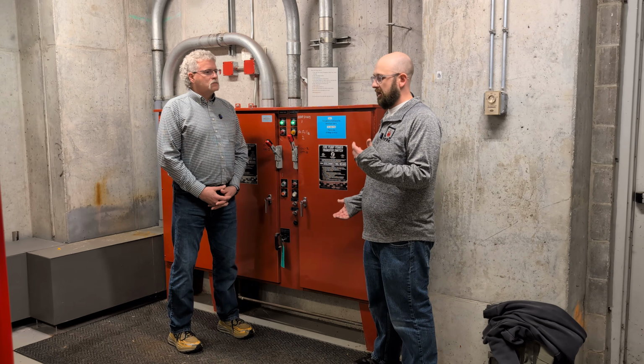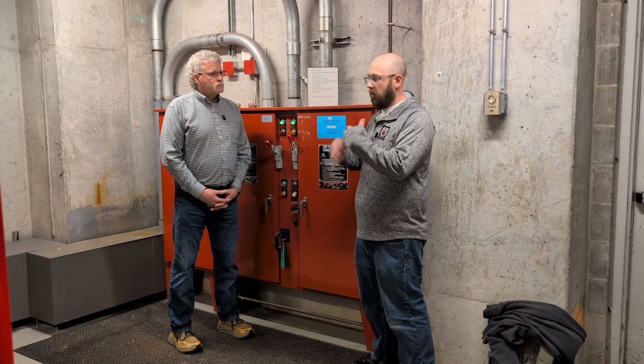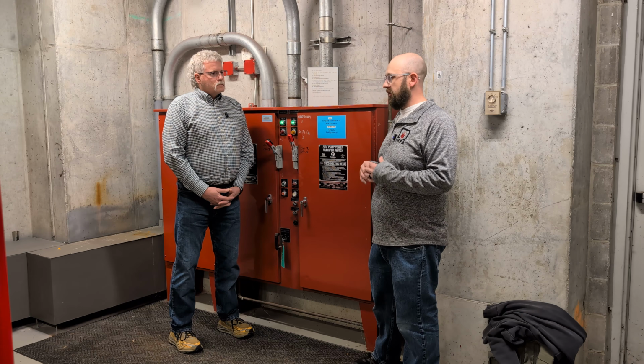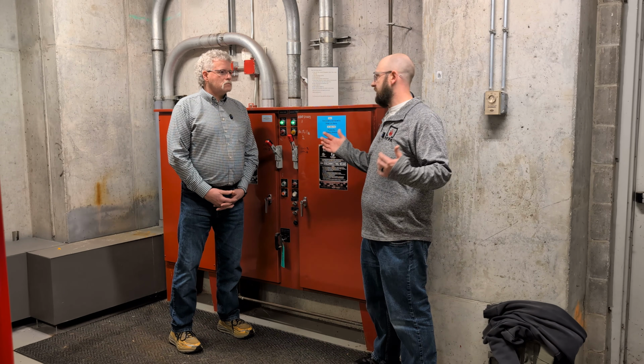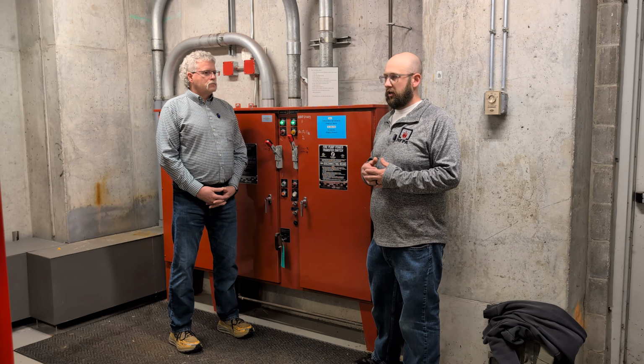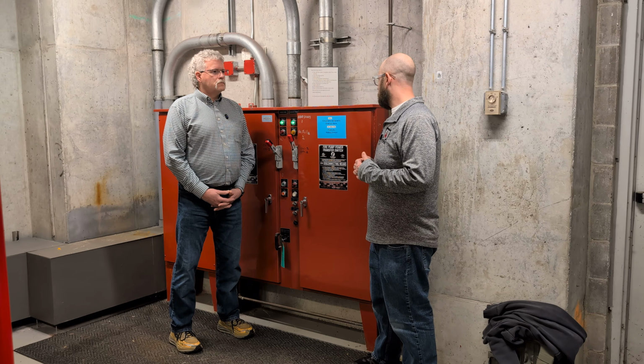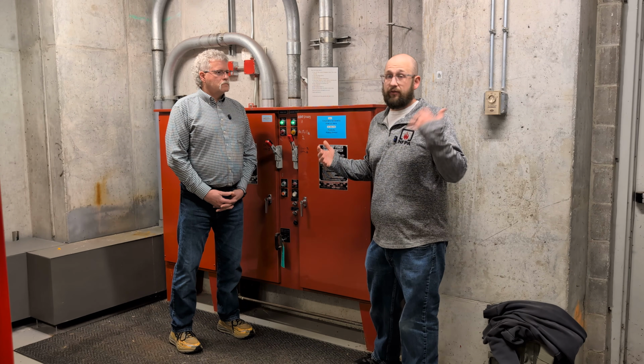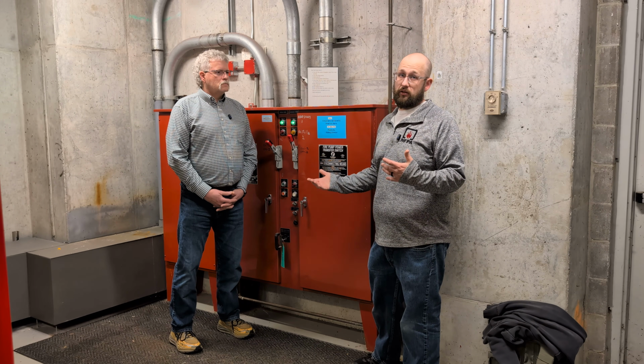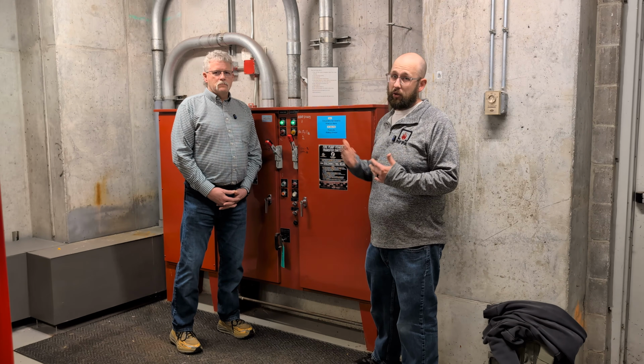Yeah, so like a case by case. And then the annex of NFPA 20 has some stuff you can look at, like the time frame in which you experience outages and things like that. You can always look at that. And the other time you would need it is if you're a high-rise building, then you need an alternate source of power regardless of whether the primary is reliable or not.